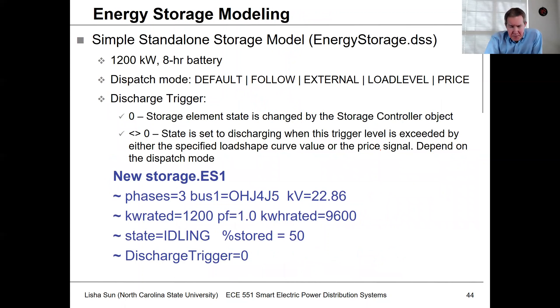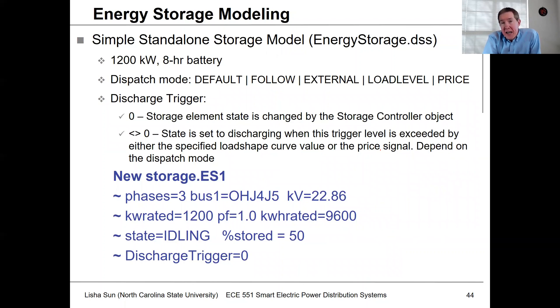Another solution is to use energy storage. When PV output is too high and causes overvoltages, we simply use the energy storage device to absorb that power at those particular times. We could also use the energy storage device to shave peak load at the top of the circuit — monitoring that point and using peak shaving control.